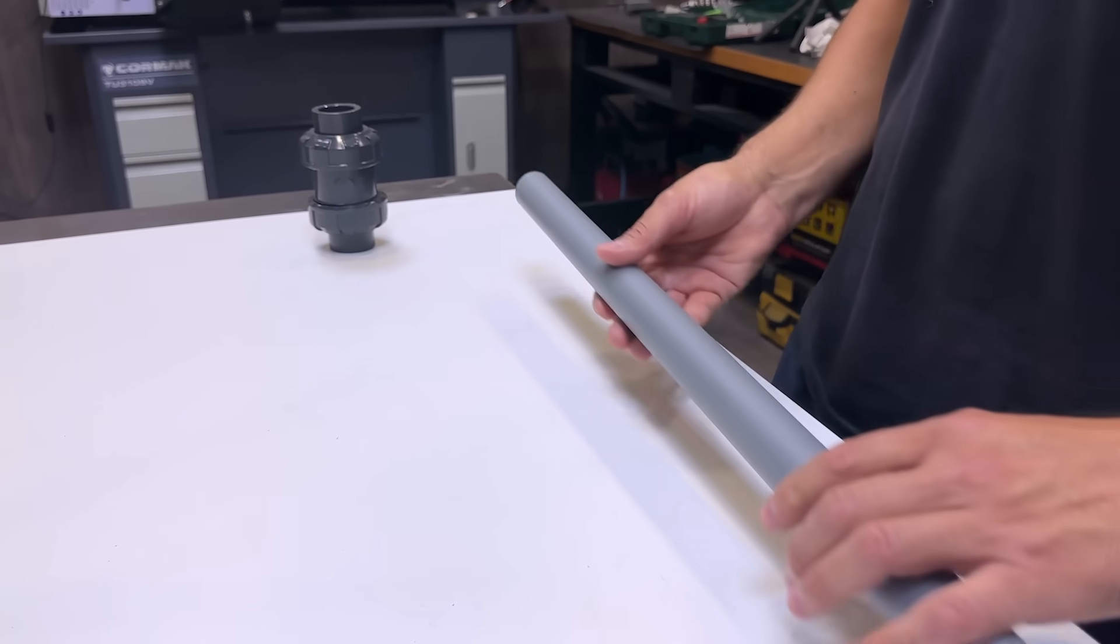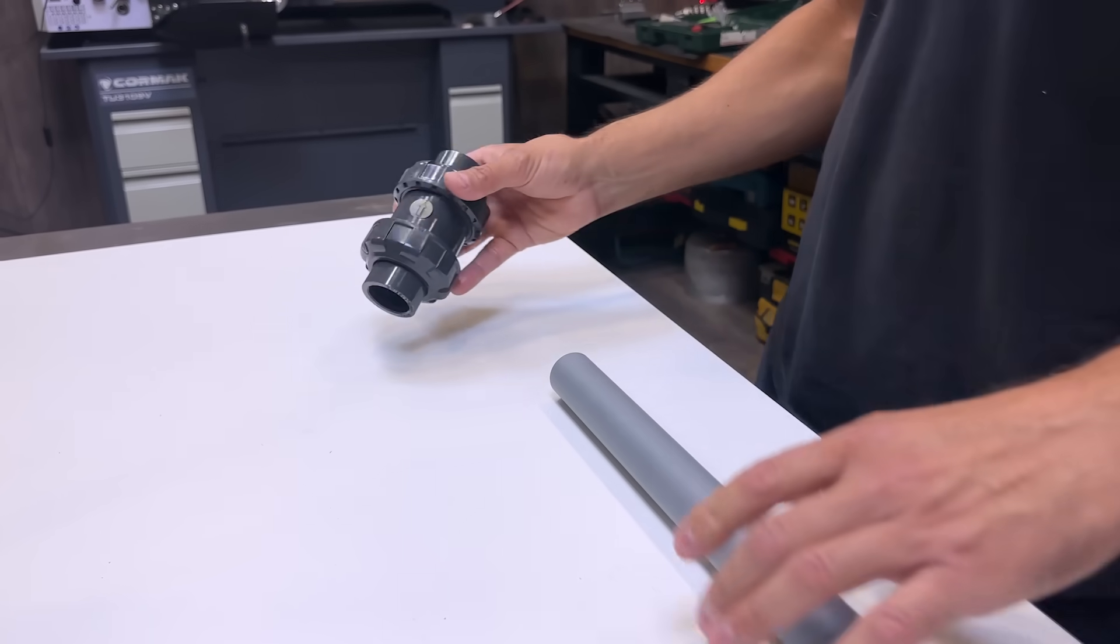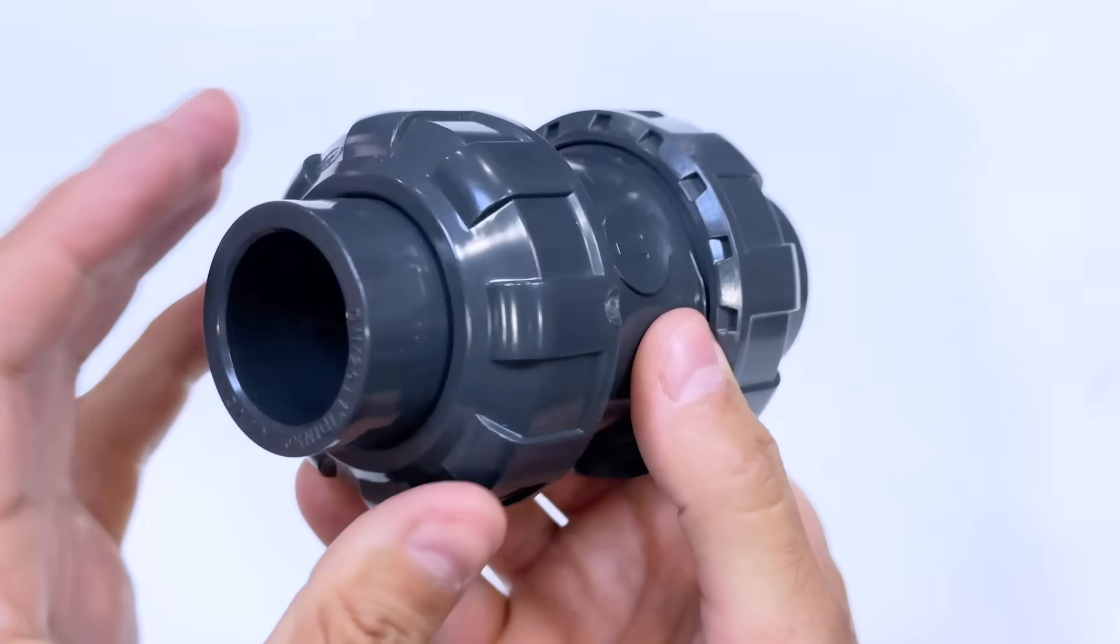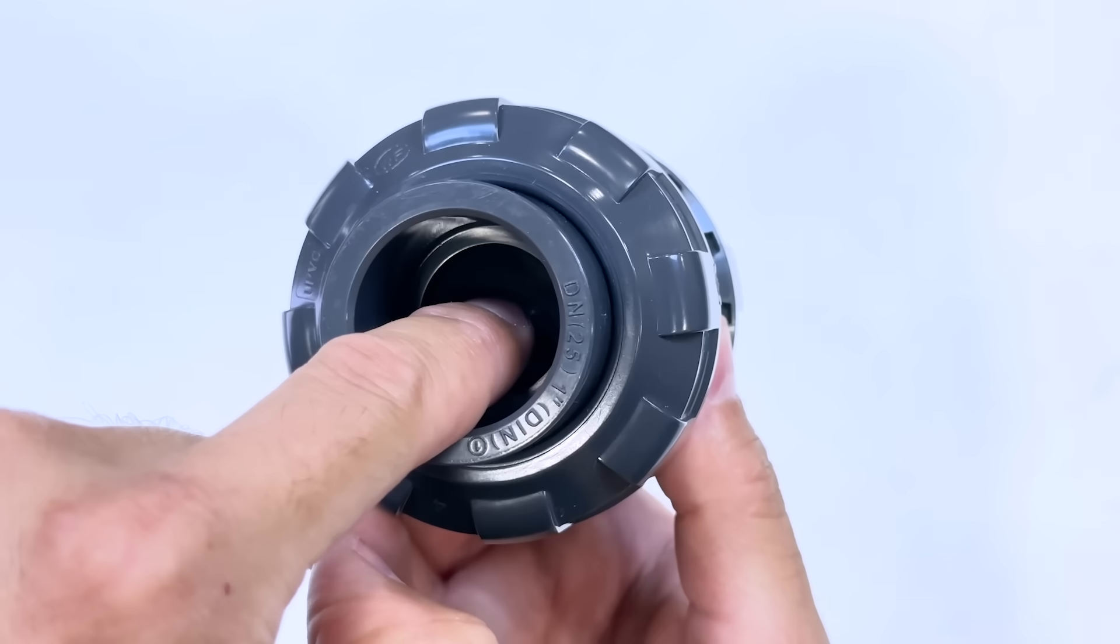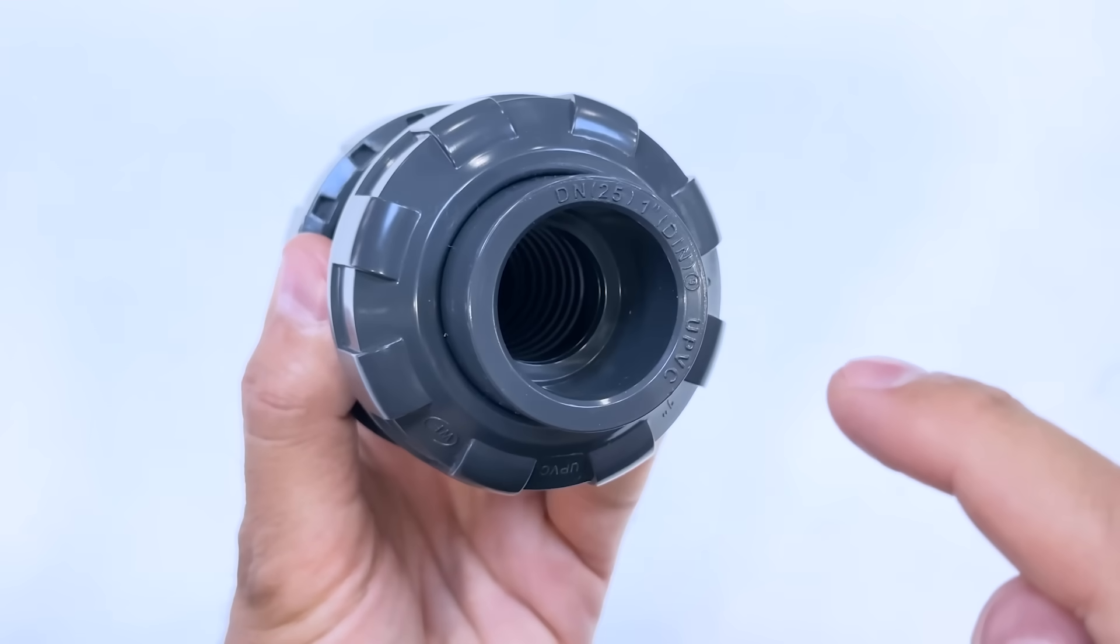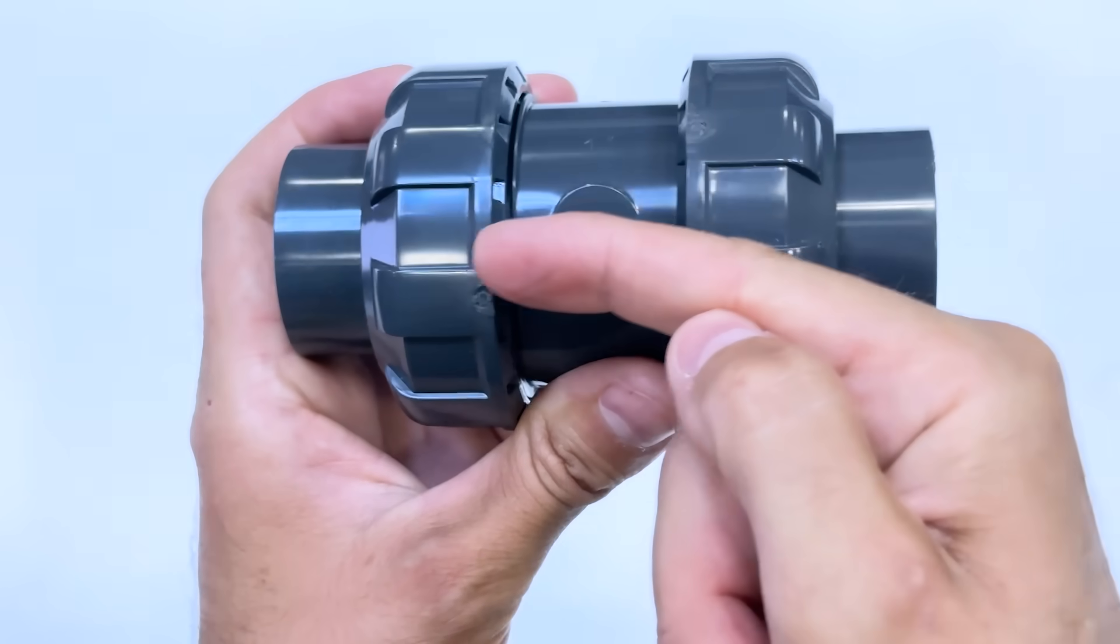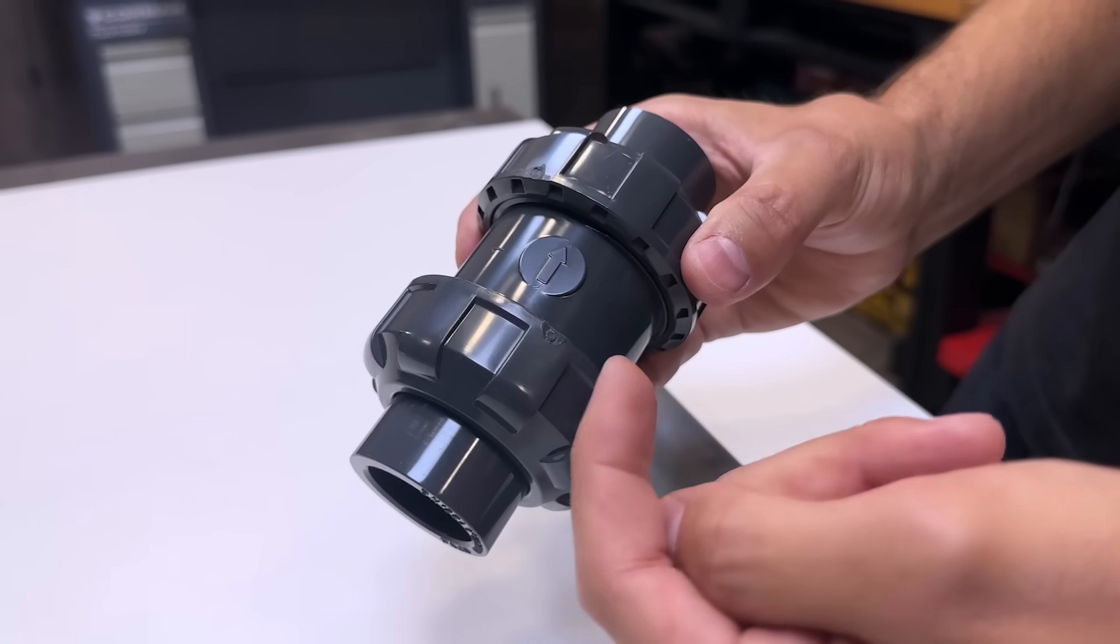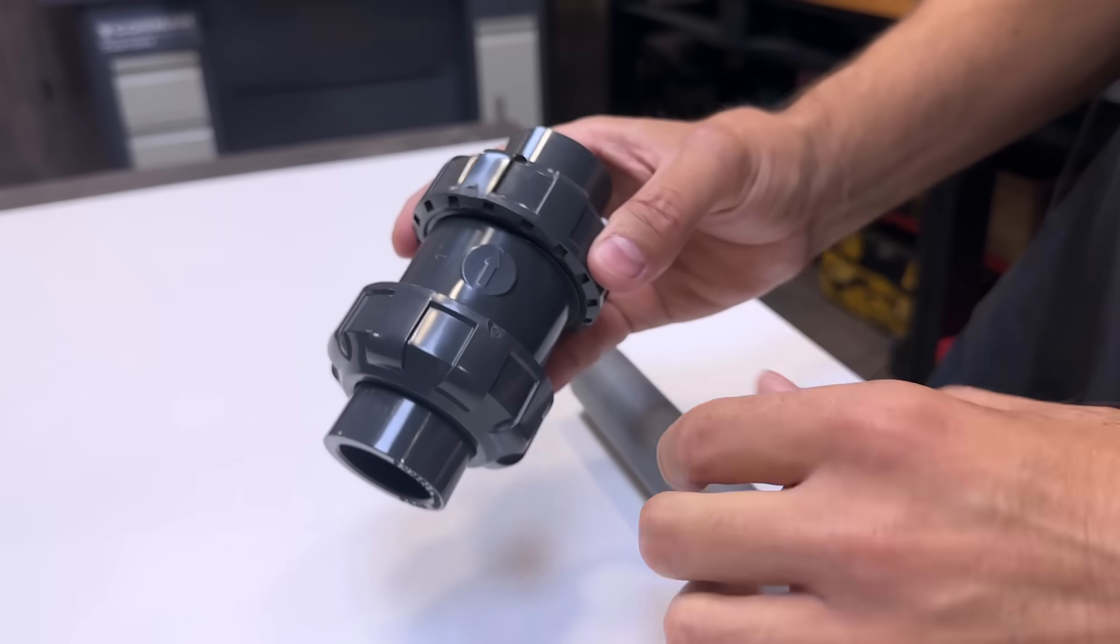This will be our water suction pipe. We need to add a non-return valve. This ball is spring-loaded. In the direction of water flow inside this valve, the ball yields and allows water to flow. In the opposite direction, the ball will block the water flow. This arrow indicates the direction in which the water will flow.